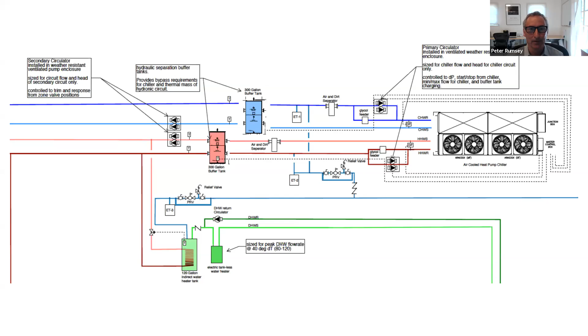One thing we spend a lot of time thinking about and designing is buffer tanks. You can see the blue buffer tank for the chilled water and the red one for the hot water. Heat pumps really like buffer tanks. When designing them in, work with the manufacturers or your local rep to make sure you're getting the right configuration and sizing. This is really important—if you don't have buffer tanks, heat pumps can tend to cycle, leading to unstable temperatures as well as premature failure. It's a very easy thing to design in, but if you forget it, it can be a problem.